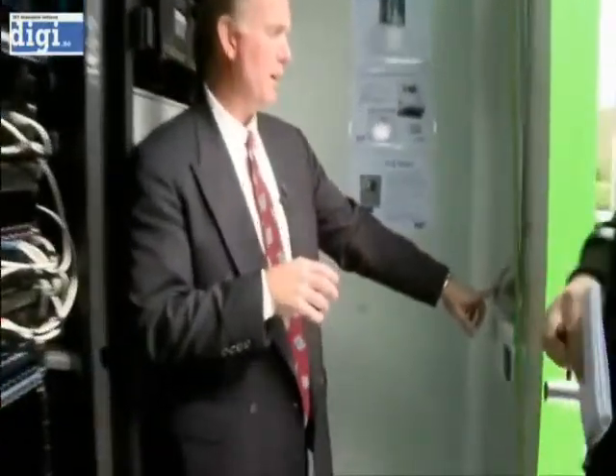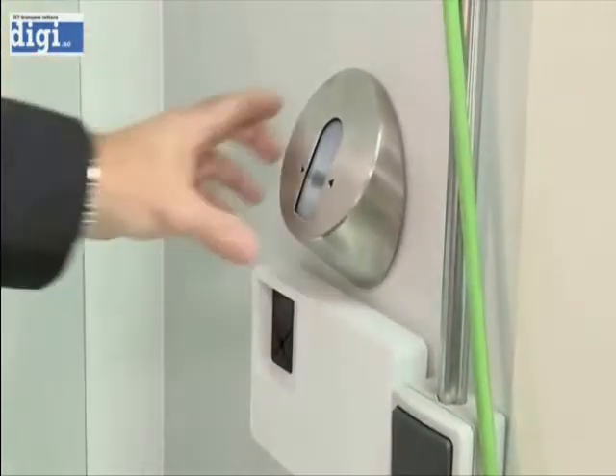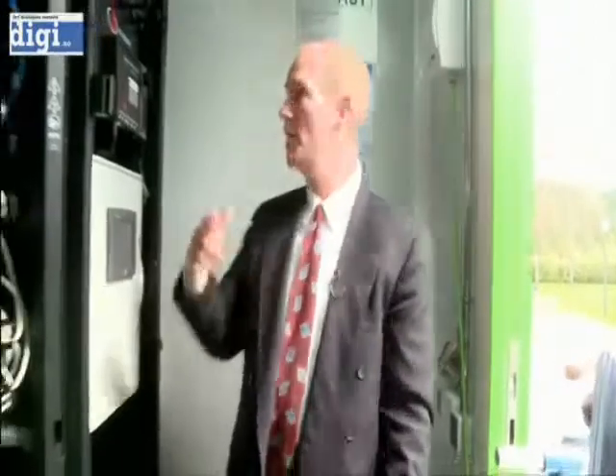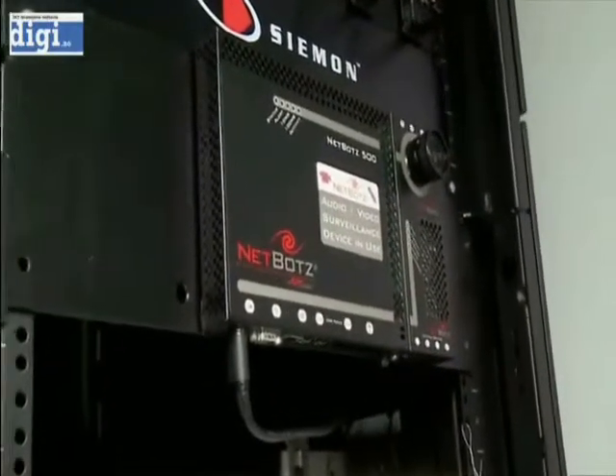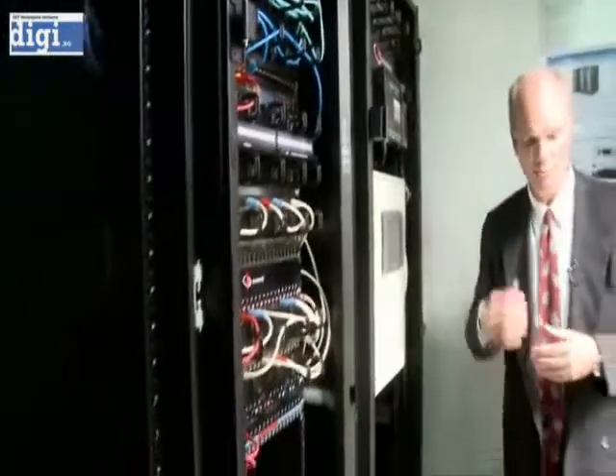As well as access. When you're coming into the Portable Modular Data Center, typically right outside the door we have an access control system, which could be a fingerprint scanner, or a magnetic card reader, or a numeric keypad. Right here we just put an example of a fingerprint scanner on the inside, only because this unit is now touring throughout Europe, so we put it on the inside just so we don't break it off. But typically you would scan your fingerprint to get access to the door. Once the door is opened and you get inside, we have closed-circuit television cameras which see who's coming in the container, so you can monitor that from any point around the world through the internet. Not only do you monitor people who might be coming in, this will also monitor temperature levels, humidity levels, leak detection, and so on. So you can monitor this unit from anywhere in the world. You don't have to be here to see what's going on.